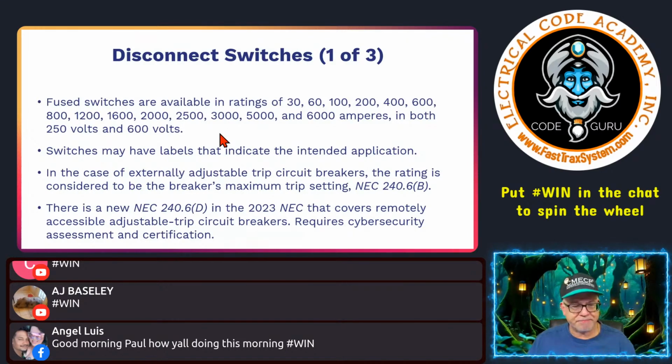I cannot complain. So when it comes to this, I don't worry about the 600 volt rating if I'm dealing with a 30, a 60, a 100, or even a 200, let's say, on a 120/240 volt system. Now, once I start dealing with 277s, 480s and whatnot, as you get further up into these frame sizes or fuse sizes, then you start worrying a little more. Obviously, you're going to have to be aware of the voltage ratings that you're dealing with.